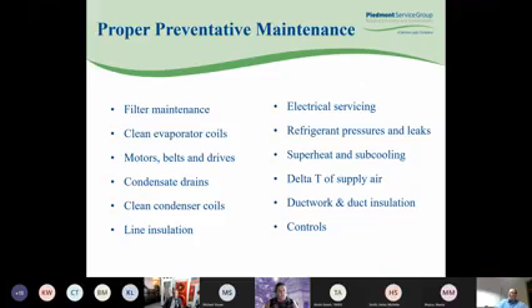Having spent a lot of time in the textiles, you have dust everywhere, and that increases the frequency that some of your maintenance needs to be performed. Filter maintenance, how dirty is the air? Filters that are allowed to stay in too long will cause the evaporator coil to get dirty or even impacted, causing airflow restrictions and freezing coils. This causes excessive runtime. The outside environment will dirty up the condenser coil, and running dirty long enough will cause the coils to become impacted. No way to reject the heat, causing compressor failures. Again, added cost and added utilities.